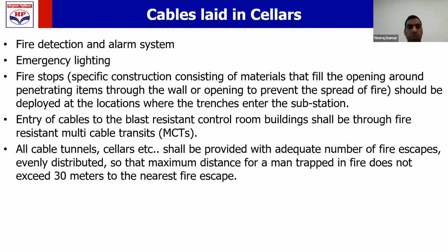If your cables are going in a control room, which is a blast resistant control room, generally refinery will have those kind of blast resistant control rooms, then cable entry shall be through multi cable transits, MCT. MCTs are a very nice medium to take the cable inside the fire blast resistant control rooms. Now, as there's a requirement for providing exit at every 30 traveling meter for substation, same requirement is also for the cellars. At every 30 traveling meter, you should provide exit.